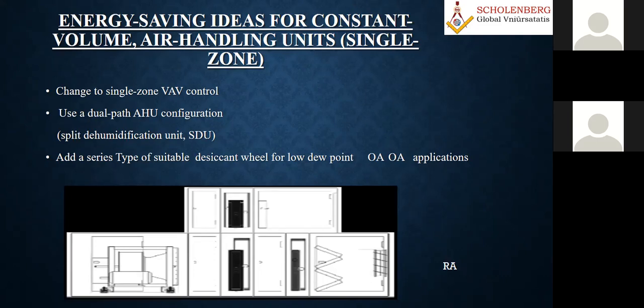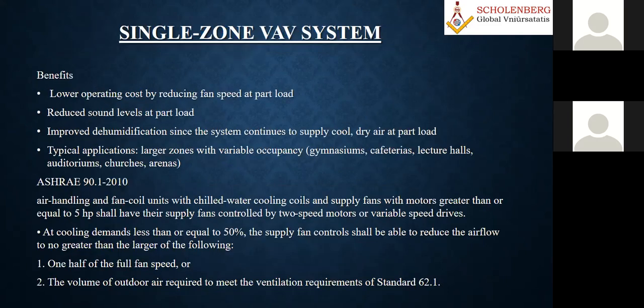Particularly in air handling, maybe you can put zone-wise, and then you also go for a variable air volume system. Maybe 30 or 40 years ago, we did not have that. We always went for a constant air volume system, but now we have different, more advanced variable air volume systems, with so many studies done. But we also have disadvantages, which I'll talk about when I discuss the air volume system, particularly the operating difficulties, especially at the terminal level.